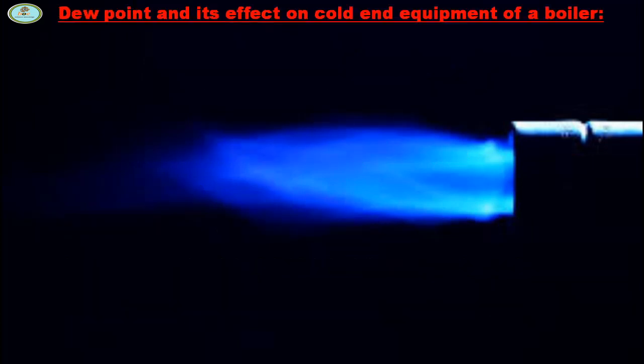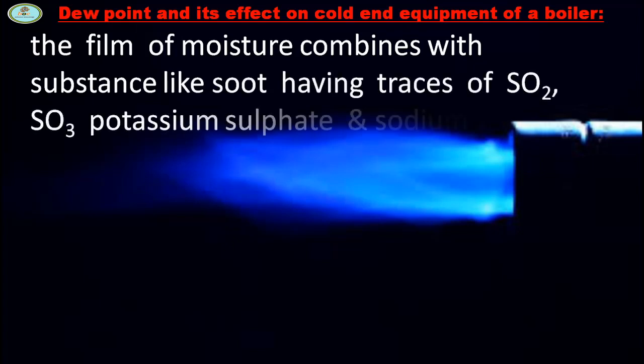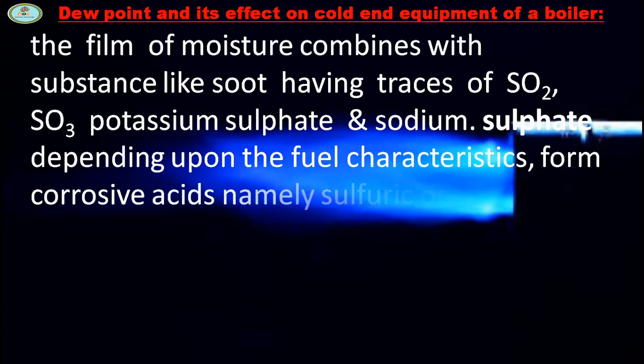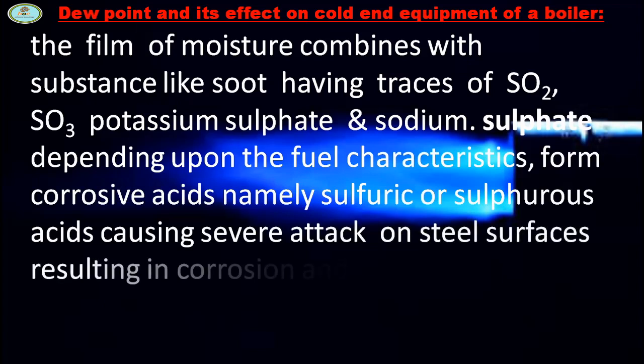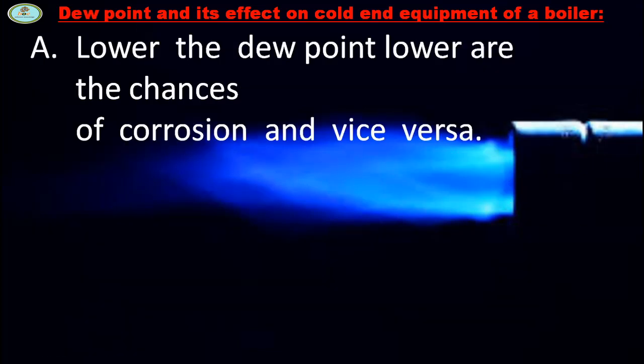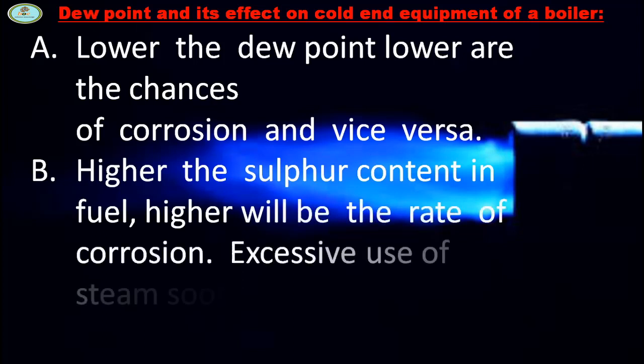Dew point and its effect on cold end equipment of a boiler: The film of moisture combined with substances like soot having traces of SO2, SO3, potassium sulfate, and sodium sulfate, depending upon the fuel characteristics, form corrosive acids namely sulfuric or sulfurous acid, causing severe attack on steel surfaces resulting in corrosion and wasting. Such corrosion is termed as low temperature corrosion. Lower the dew point, lower are the chances of corrosion and vice versa. Higher the sulfur content in fuel, higher will be the rate of corrosion. Excessive use of steam soot blowers will augment corrosion.